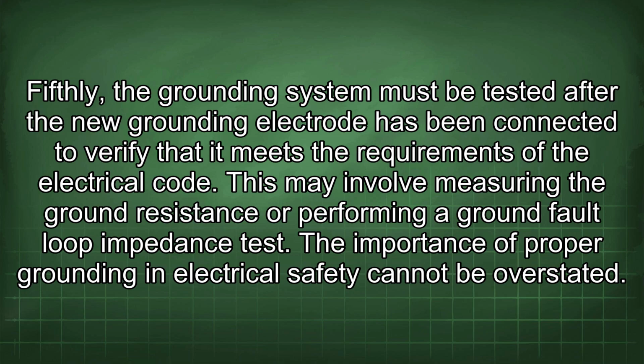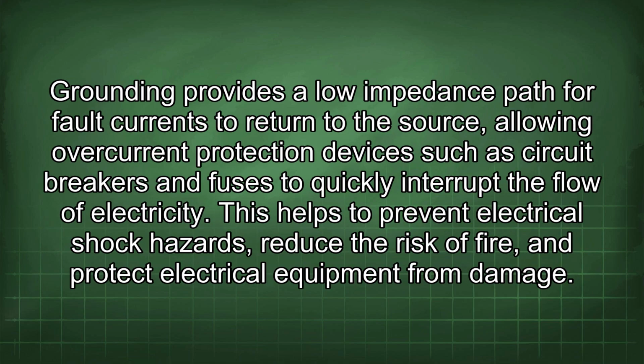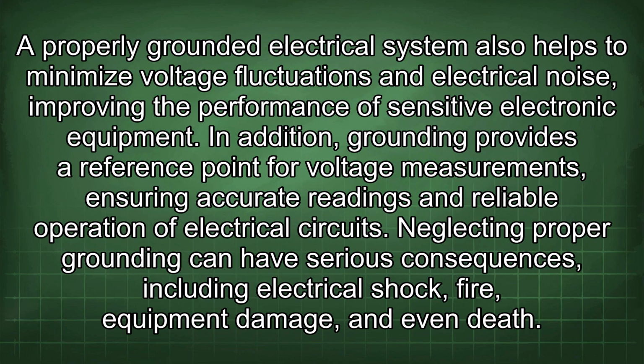The importance of proper grounding in electrical safety cannot be overstated. Grounding provides a low impedance path for fault currents to return to the source, allowing overcurrent protection devices such as circuit breakers and fuses to quickly interrupt the flow of electricity. This helps to prevent electrical shock hazards, reduce the risk of fire, and protect electrical equipment from damage. A properly grounded electrical system also helps to minimize voltage fluctuations and electrical noise, improving the performance of sensitive electronic equipment. In addition, grounding provides a reference point for voltage measurements, ensuring accurate readings and reliable operation of electrical circuits.